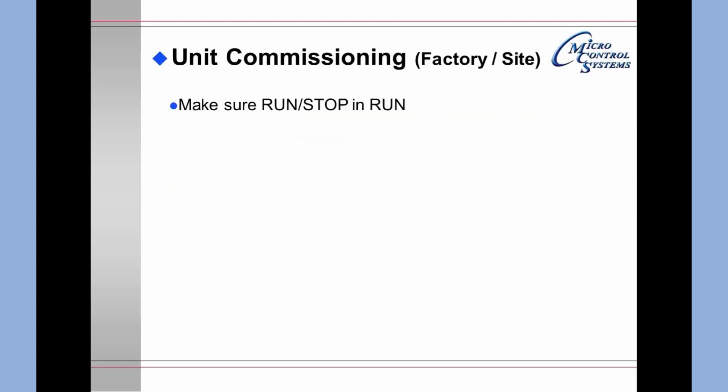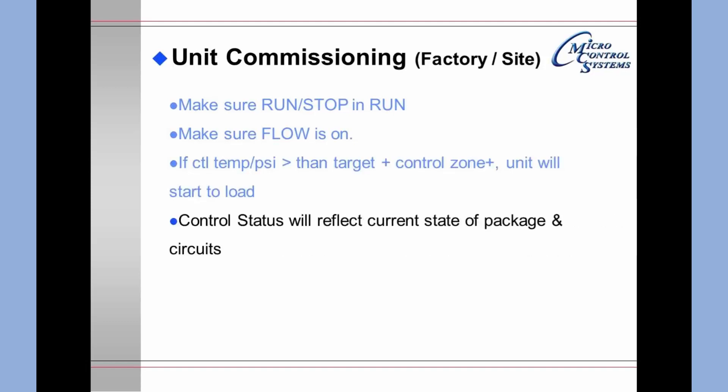Make sure that the run stop switch is in run. Make sure the flow switch is on. If the controlling temperature or pressure is greater than the target plus the control zone, the unit will start to load. The control status will reflect the current state of the package and the circuits.